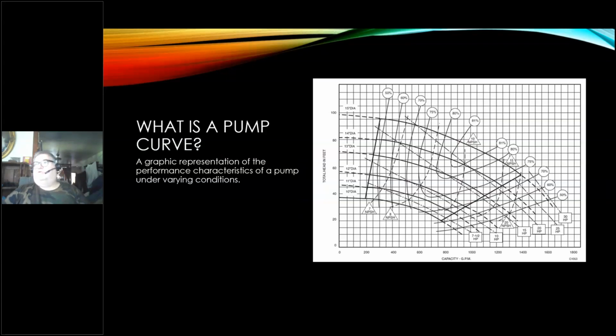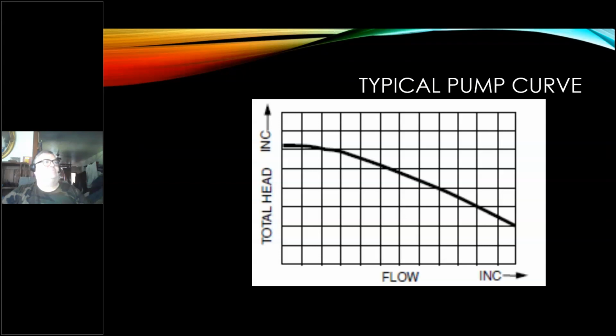So a pump curve is a graphic representation of the performance characteristics of a pump under varying conditions, okay? So each one of these curves represents an impeller. We'll go through the parts of it piece by piece. This is a typical pump curve. The critical parts are the vertical lines, the lines going straight up represent the head produced by the pump against the flow, which is going across the bottom.